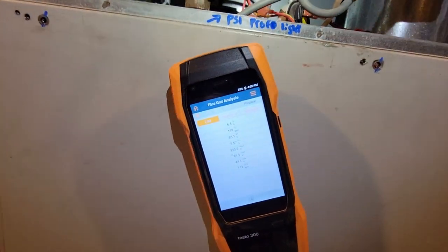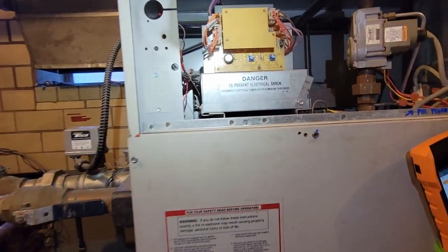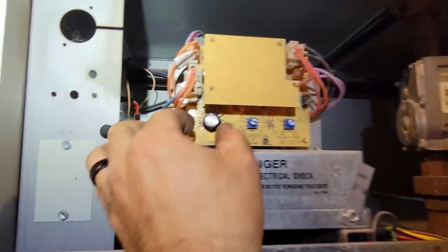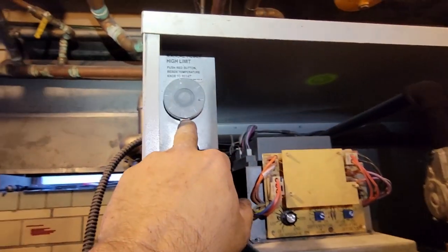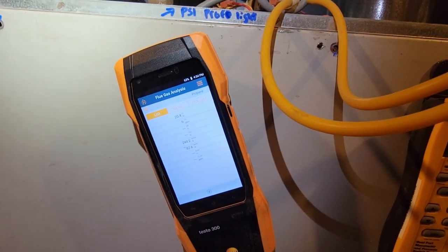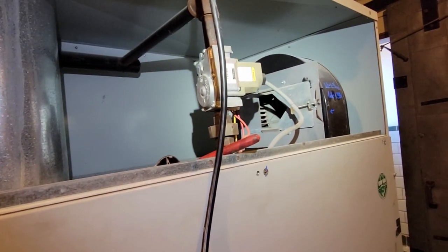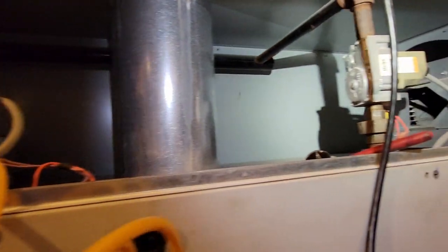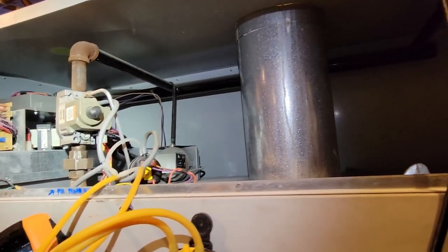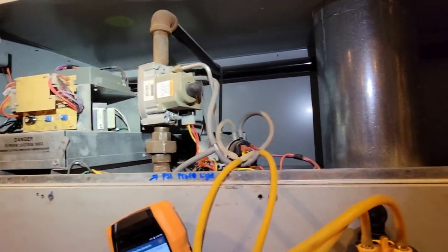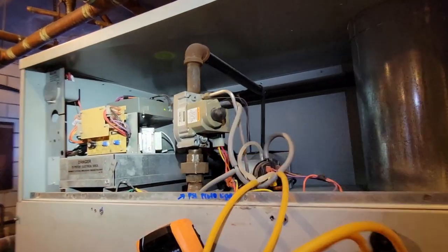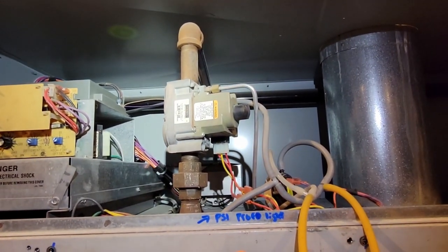Obviously had too much fuel, incomplete combustion. It's fairly warm out so it's satisfied. I set that back down to 160, which is where they had it at. The limit set for just about 175. It's running cleaner, we're under 200. Just took a half a turn. I didn't check the pressure yet, but I know when I was coming up to it, it took several turns to get up to it, so half a turn is not going to do anything much. That's crazy.